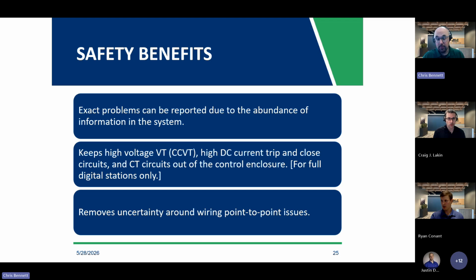As mentioned before, there's also major safety benefits to CPC. Because we are now reporting exactly what is wrong with each individual device. So traditionally in a transformer, we will gather the major alarms and tripping outputs for use in our protection system. We leave behind a lot of alarms in all devices, such as the first warning signs of loss of oil, loss of temp, loss of you name it. All of these now can be reported and exact problems can be tracked with asset management software. So replacements and failures can be mitigated.